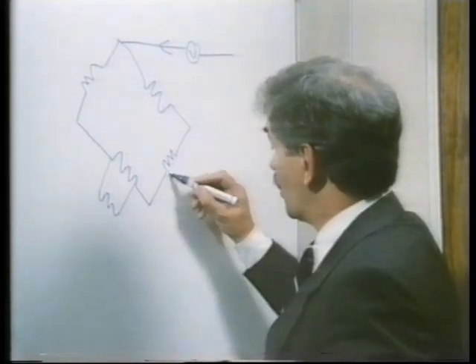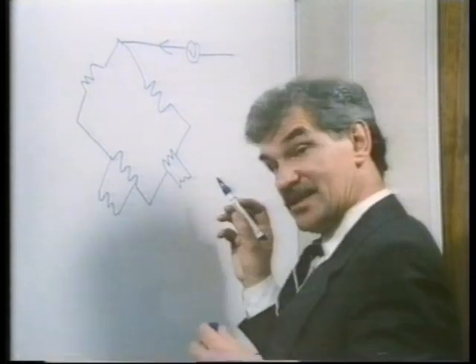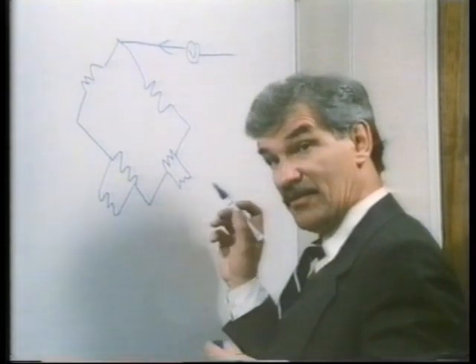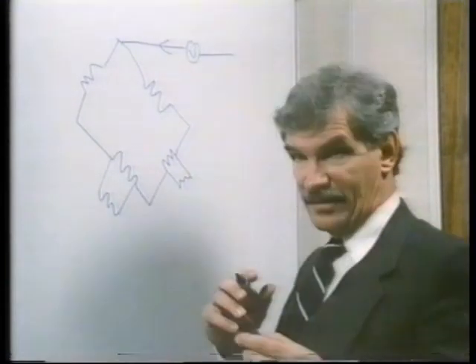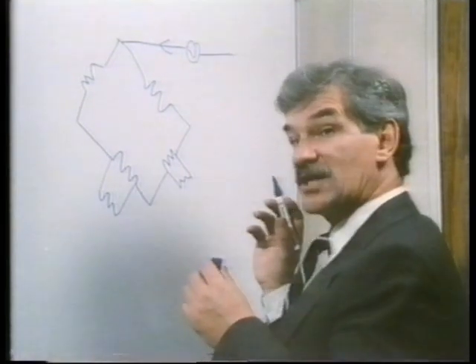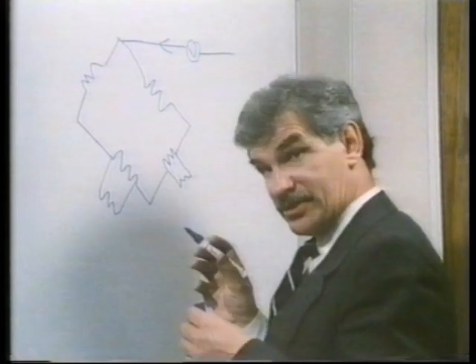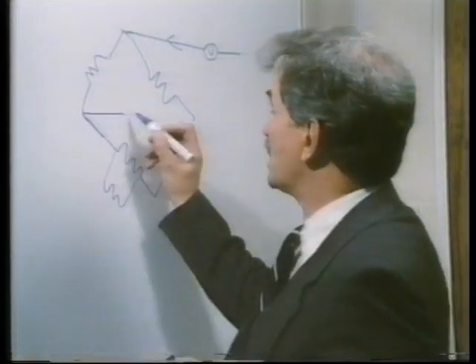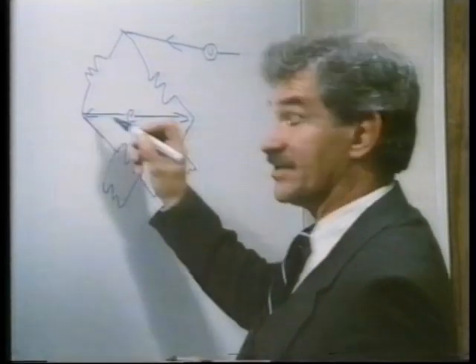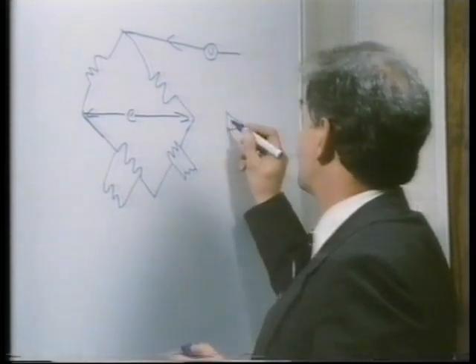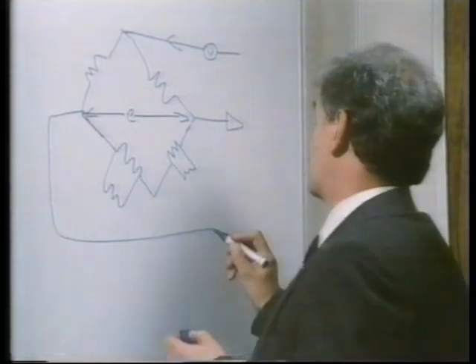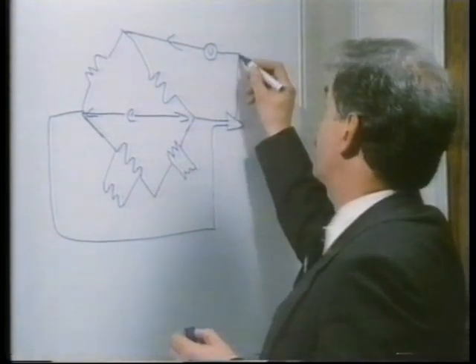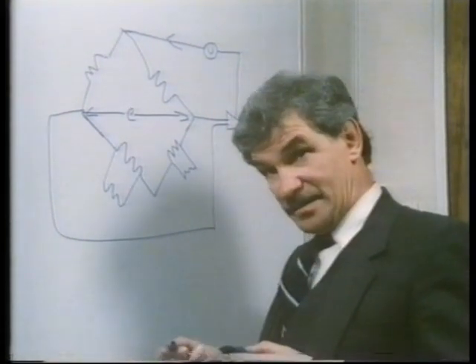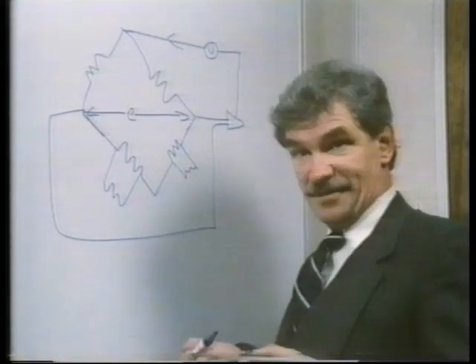Correct. Now, at this end of the bridge, we have a thermal sensor that's measuring the temperature of the fluid. So that compensates for any fluid temperature changes? You've got the idea. The system maintains a constant balance between the transducer and the fluid. So if the fluid velocity changes, we get an error signal across the bridge. A servo amplifier varies the electric current until it restores equilibrium. Those variations in the current are a direct measure of our flow rate.